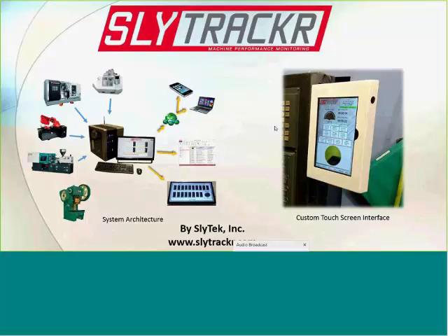And then we still had a tablet at the machine, but we were originally using thin clients. What we realized with thin clients is they work great, but we found we had a lot more opportunity with an actual runtime license at each machine versus a thin client. So we switched over to that, where we have a server, like I said, and then each touchscreen interface at the machine is actually running its own runtime license. And that's how we're able to communicate with the module.